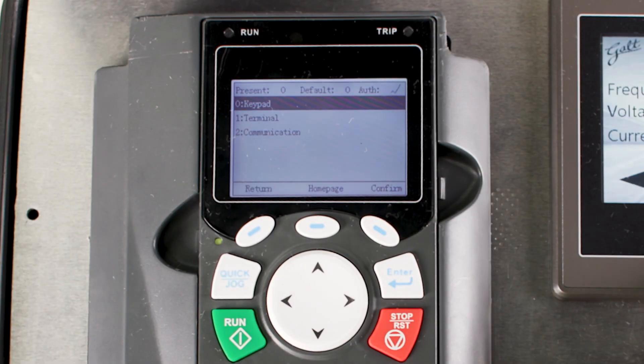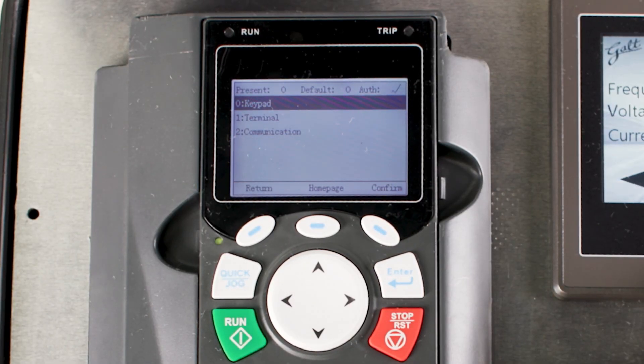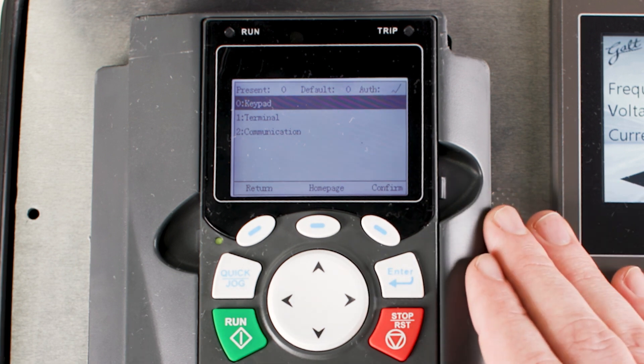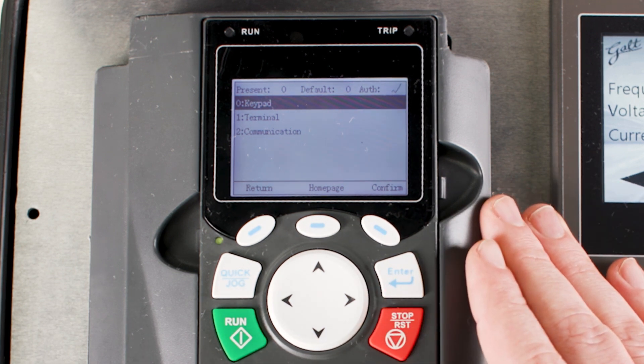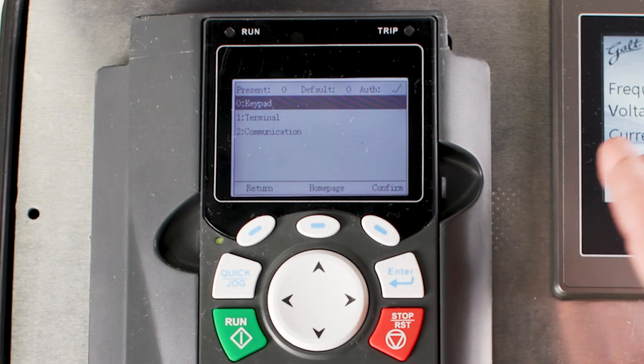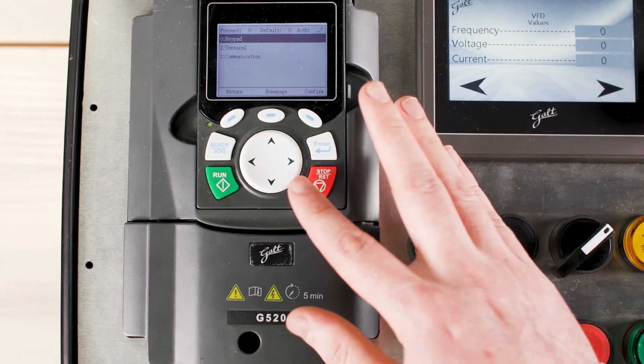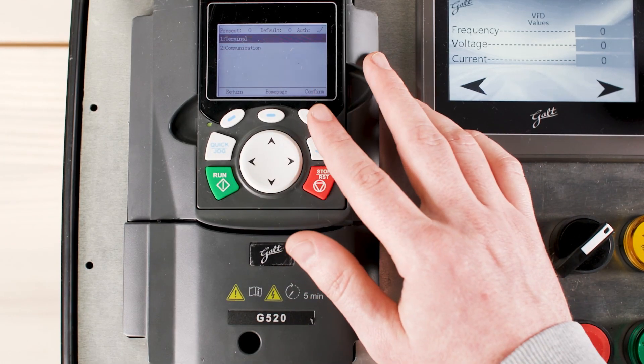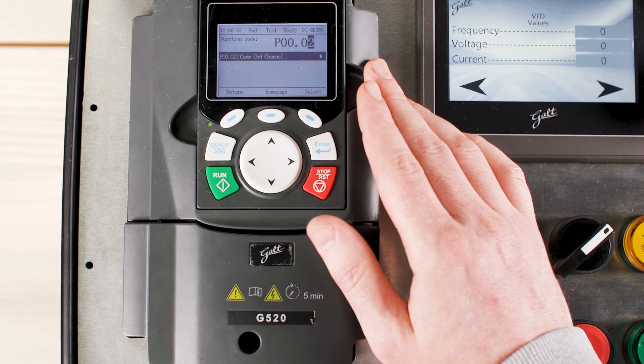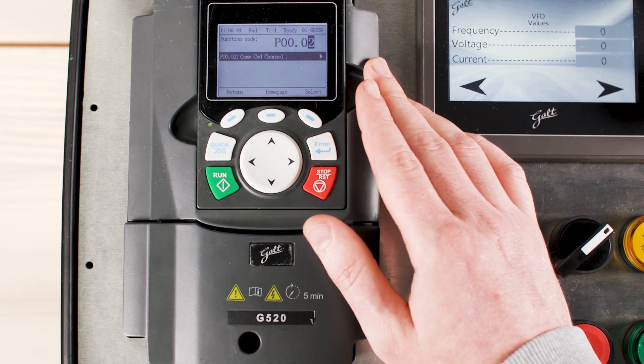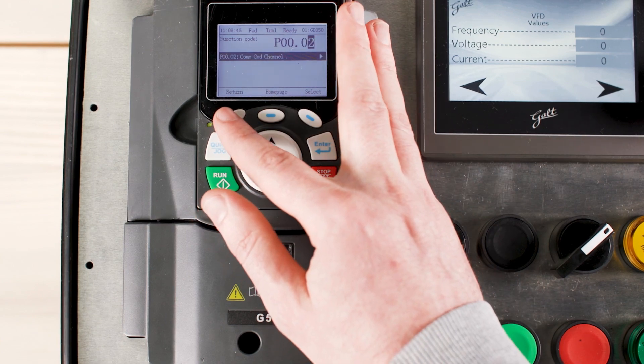Press up on the directional pad to show parameter 00.02 and press the right function button to select the parameter. Now that we've selected 00.02, we can see the available options within the running command channel parameter. The drive is set default to keypad controls, but if you wish to control the drive with the terminals, you would press down on the keypad and press select to change the parameter to 1 for terminal operation. To back out of this parameter, press the left function button to return to the previous parameter.